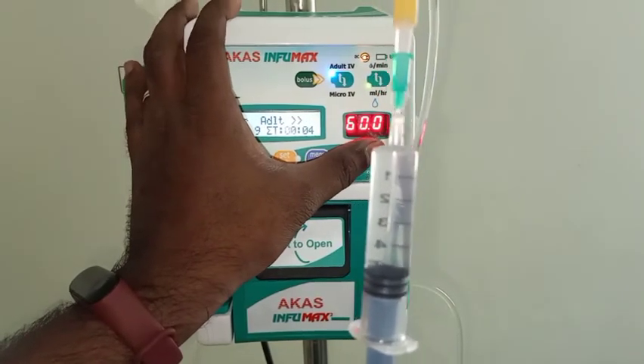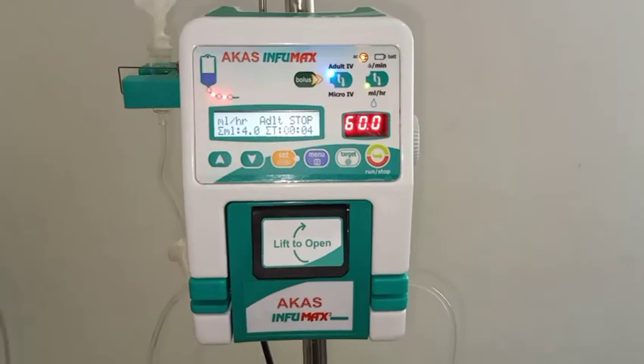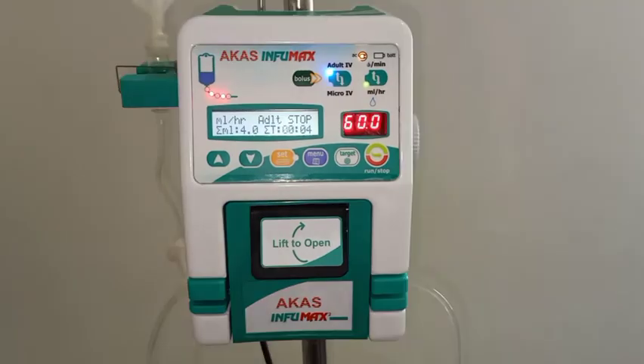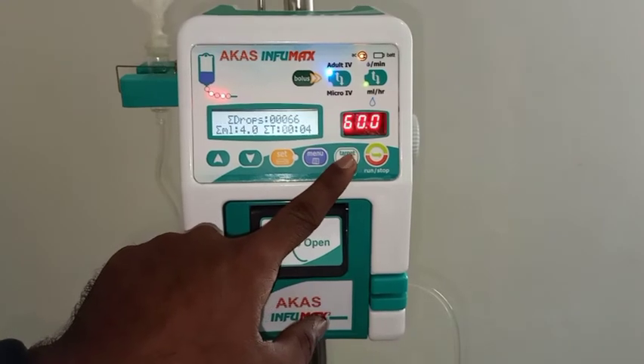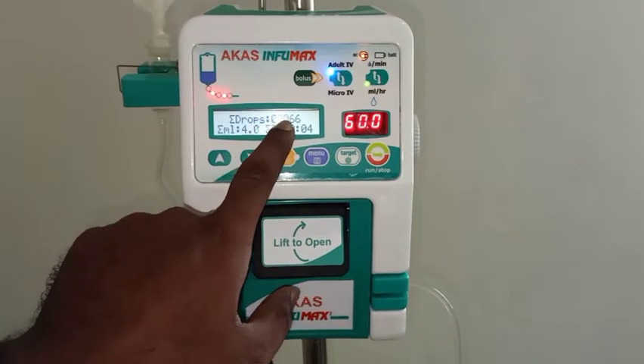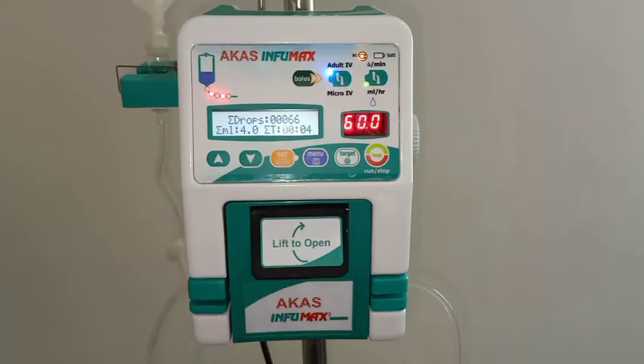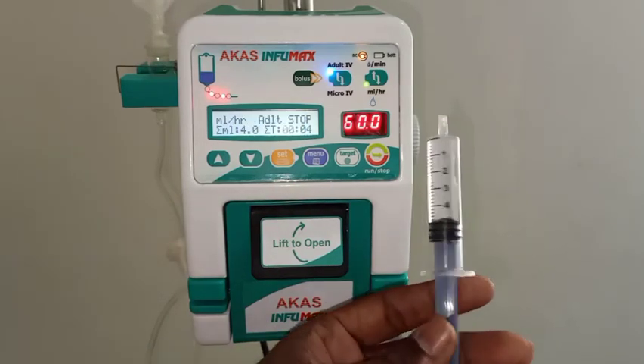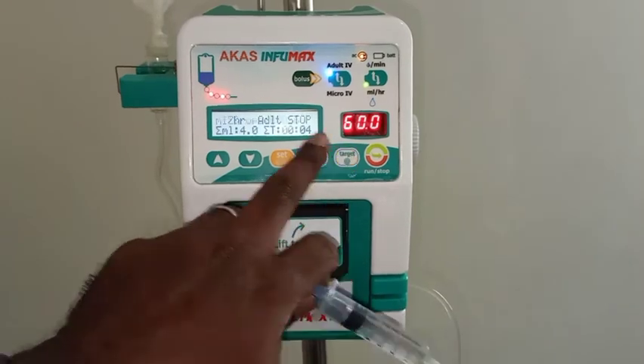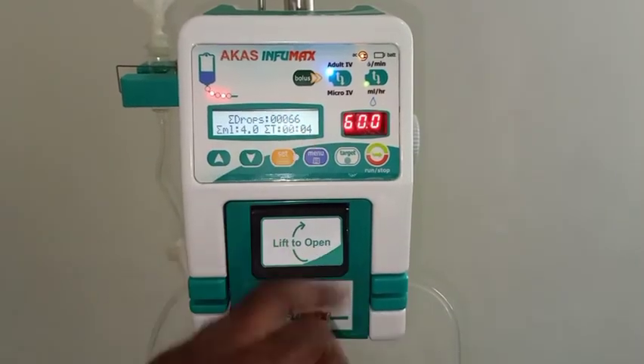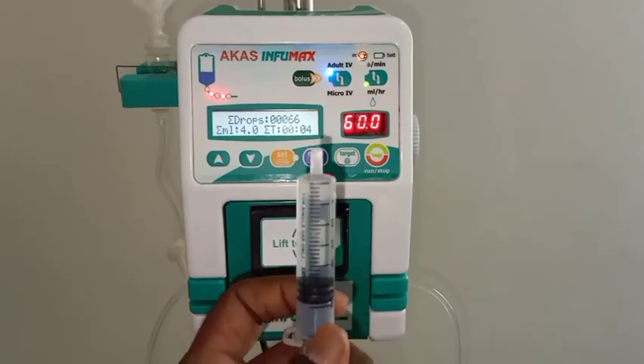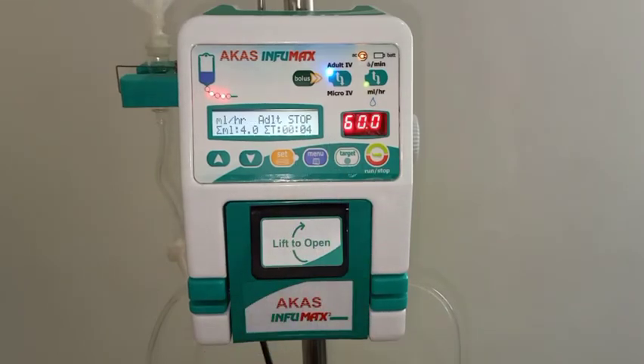So while the syringe has filled, just press the run key to stop the pump and press the target key. Here you can see the elapsed drops as 66. We have collected 5 ml, so the target elapsed drops is 66. So we have to divide the value by 5. 66 divided by 5, and the value is 13.2.